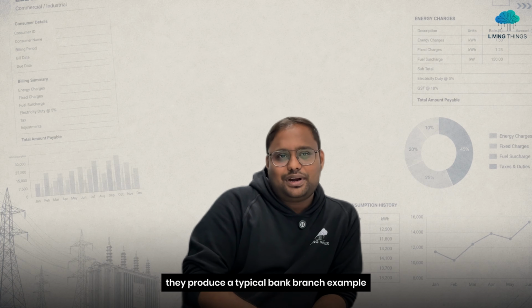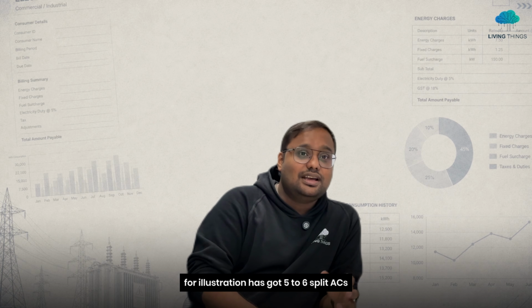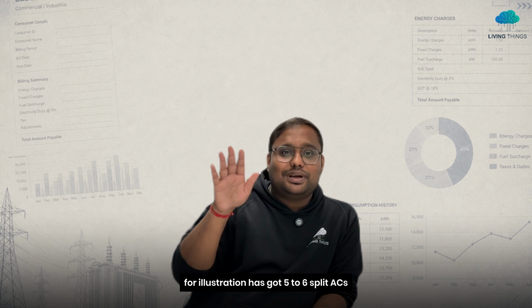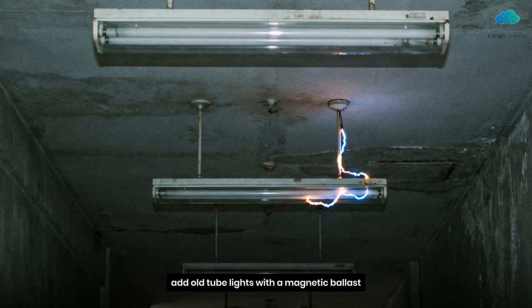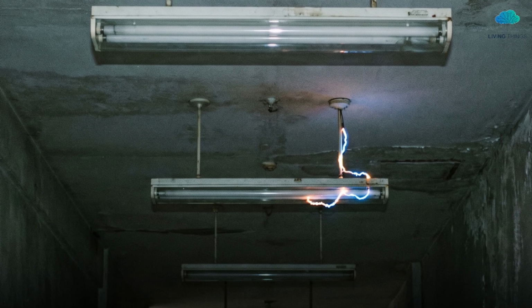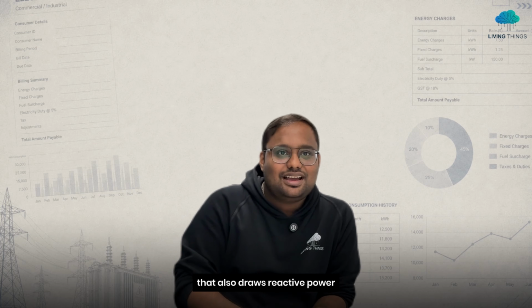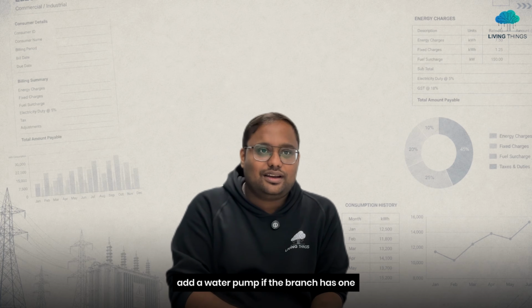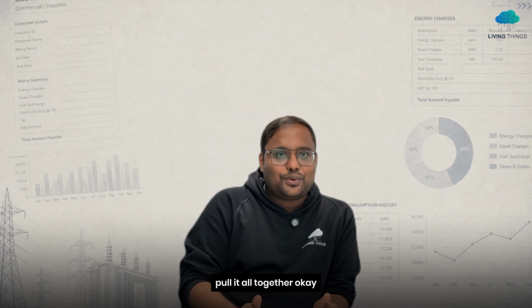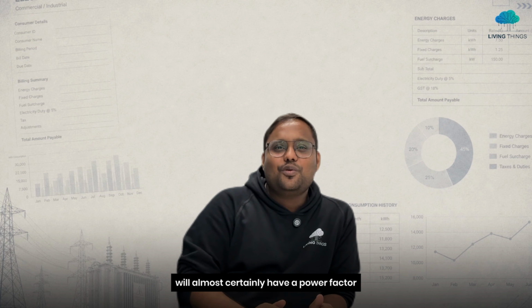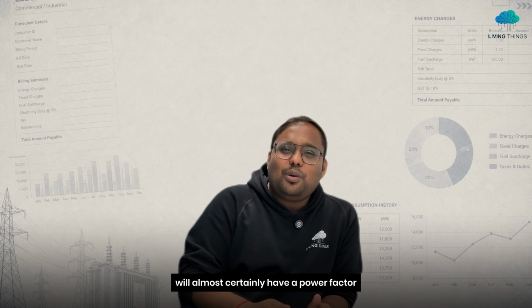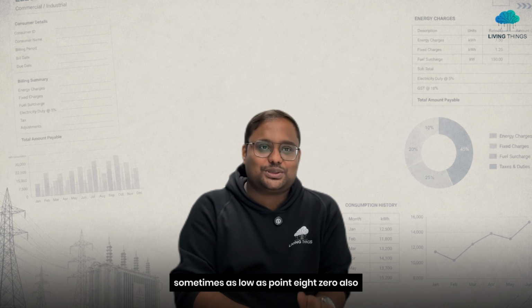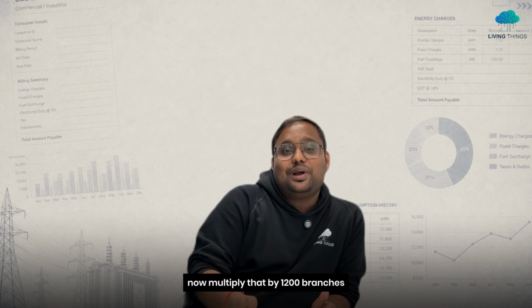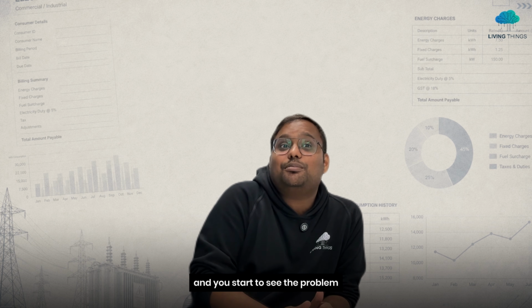A typical bank branch, as an example for illustration, has 5 to 6 split ACs. Add old tube lights with a magnetic ballast. That also draws reactive power. Add a water pump if the branch has one. Pull it all together, and a branch with older equipment will almost certainly have a power factor below 0.90, sometimes as low as 0.80. I have seen 0.4 also. Now multiply that by 1200 branches and you start to see the problem.